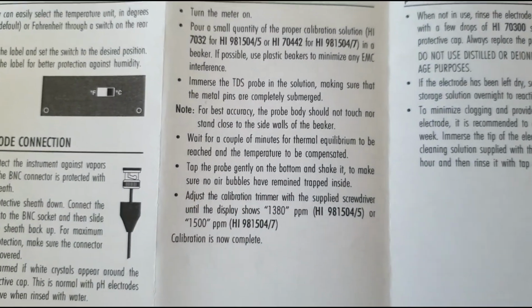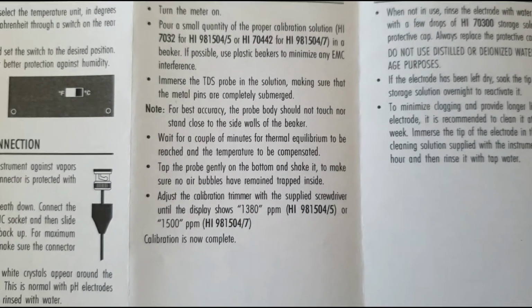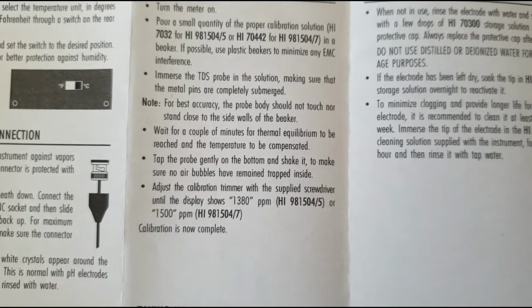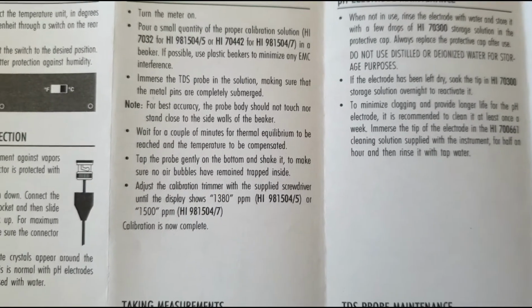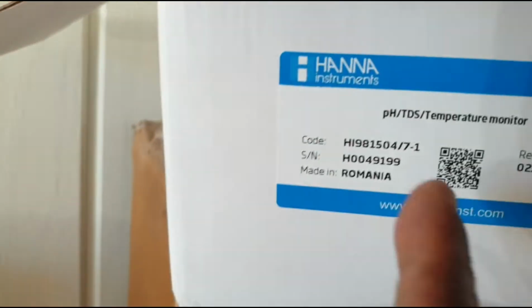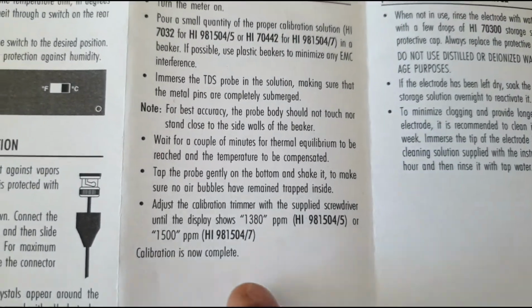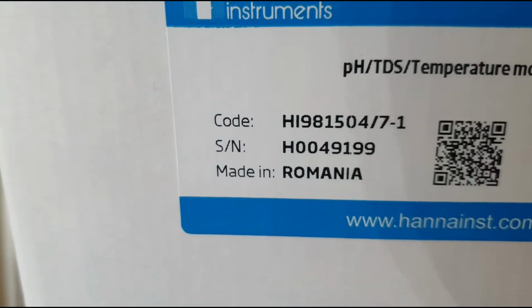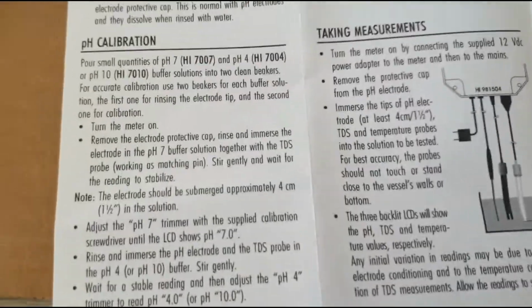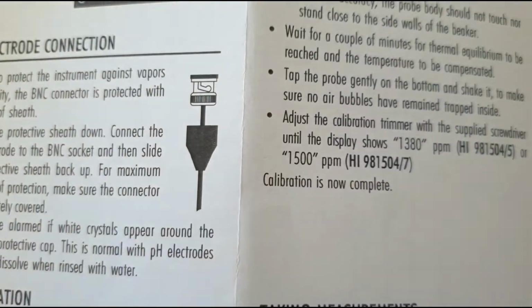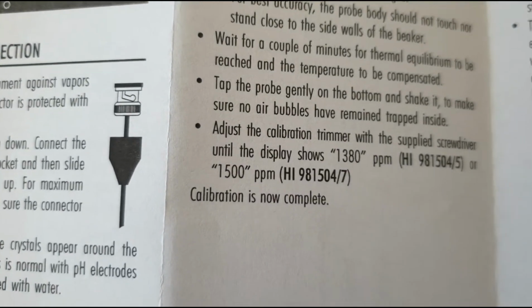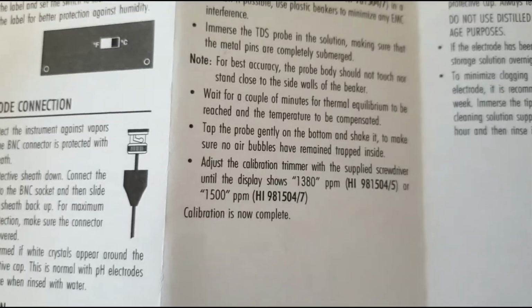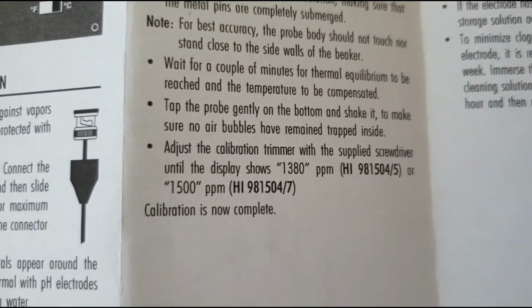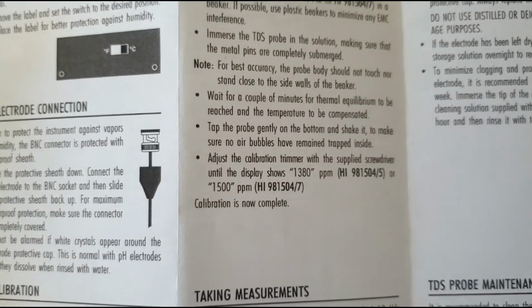adjust the calibration with the supplied screwdriver until the display shows 1380 ppm, and in brackets they give you a code, or 1500 ppm, and in brackets they give you a code right here. So the code is basically this code that I showed you on the box, which is the code of the meter. Depending on the code of your meter, you will choose one of those ppm values. So the code of this meter is, as you can see, 981504/7. And as you can see here, it says HI981504/7. So we would calibrate the ppm to 1500.